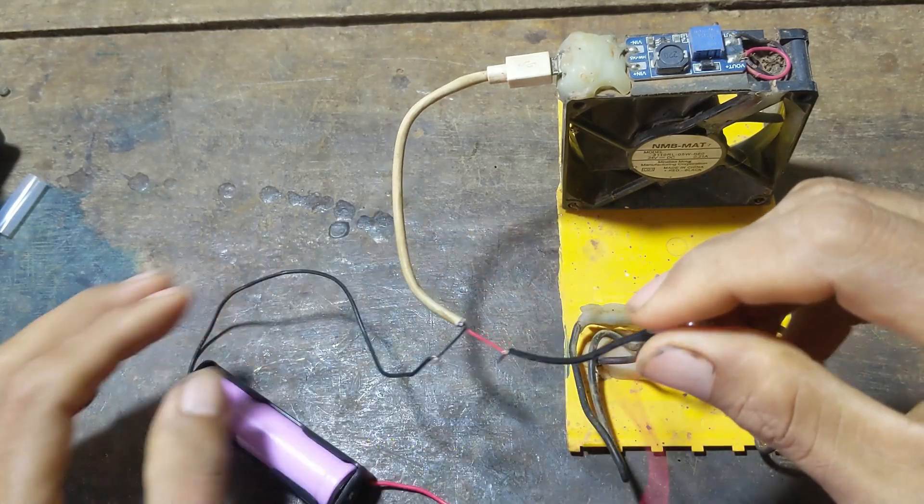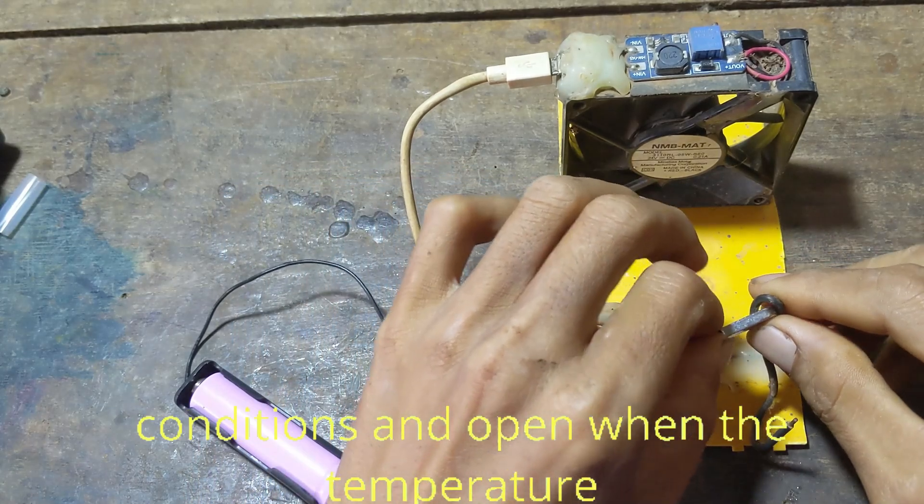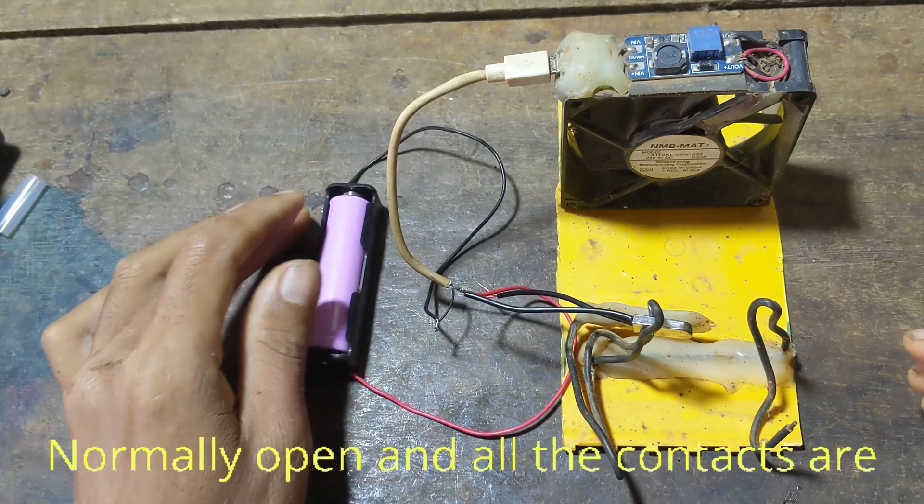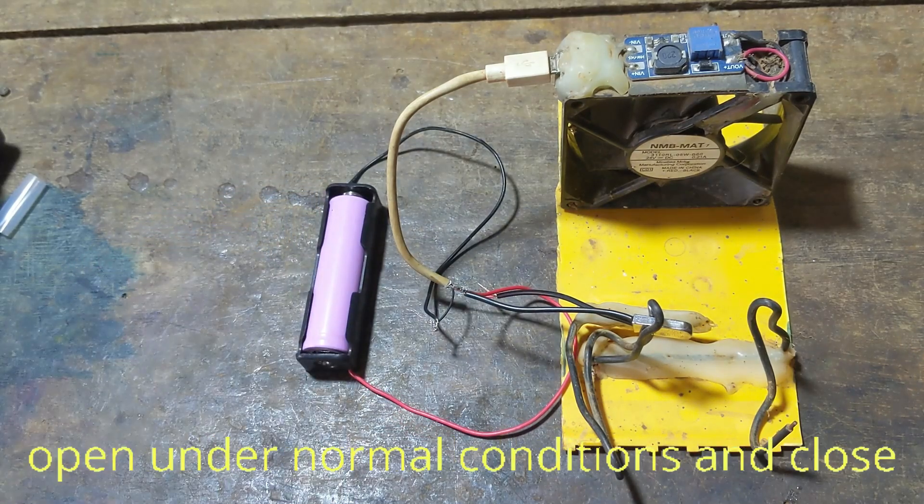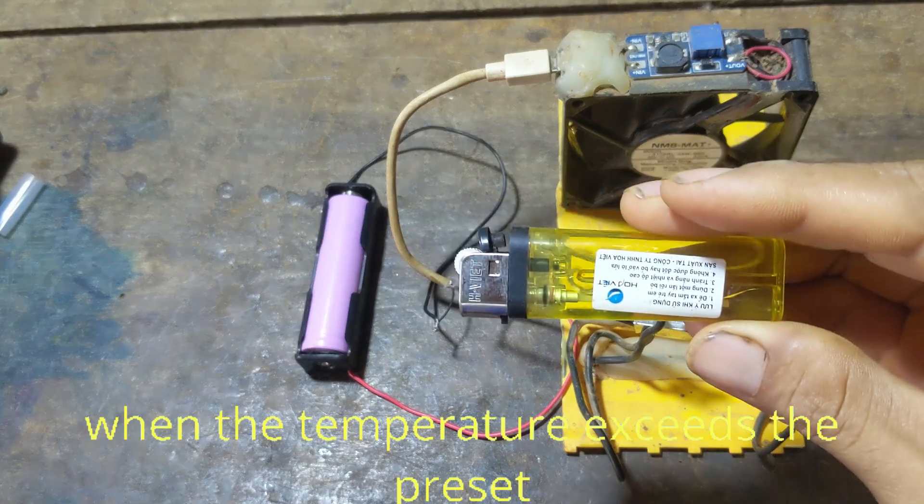Normally closed (NC): the contacts are closed under normal conditions and open when the temperature exceeds the preset value. Normally open (NO): the contacts are open under normal conditions and close when the temperature exceeds the preset value.